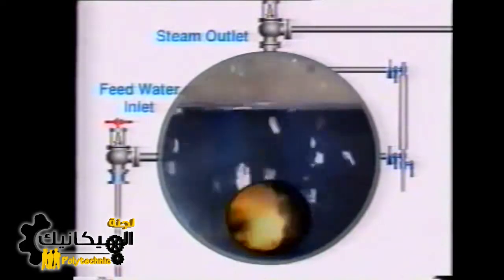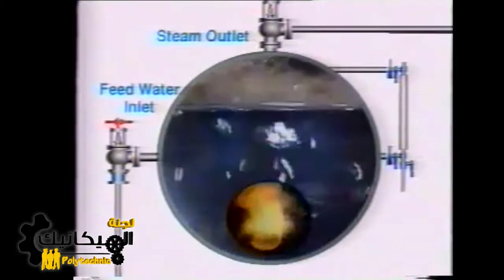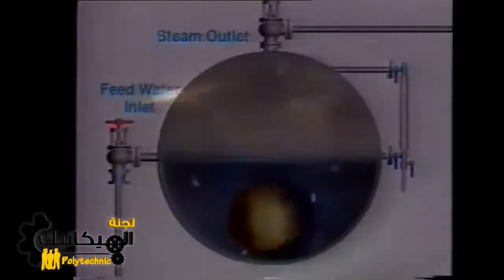None of this is apparent in the gauge glass or the protection tube, because they are measuring virtually bubble-free water, and the water at the top of the boiler consists mainly of steam bubbles. The measured levels begin to fall as water continuously flashes into steam, in the boiler's attempt to satisfy the excessive demand. Eventually, the first low-level alarm is triggered. This shuts down the burner and the bubble-charged water drops very rapidly. It soon becomes apparent how little water is left in the boiler. So little, in fact, that the stay bars become exposed.